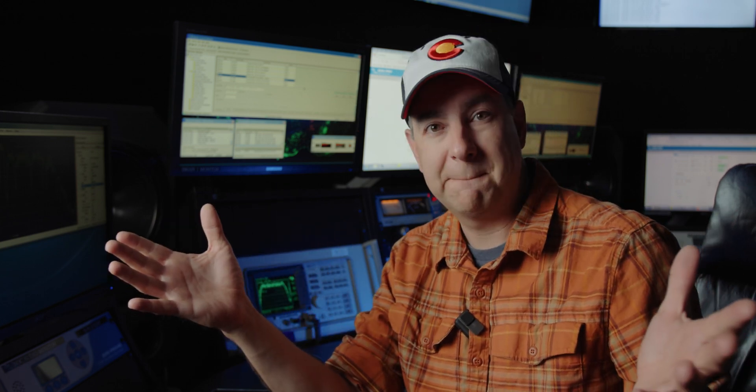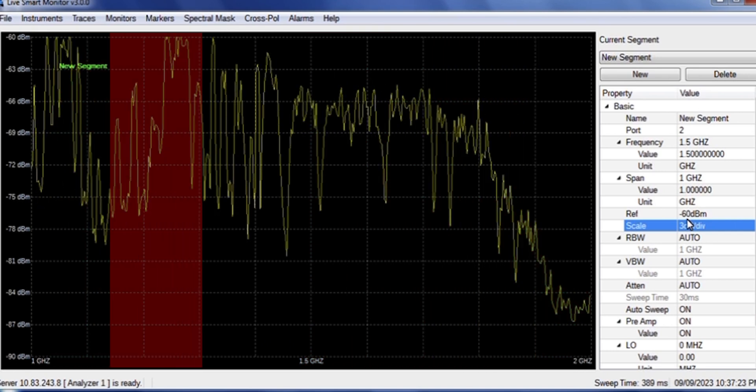Now, what our resolution bandwidth is, is how wide that window is. So if you are looking at a very large signal, a wider resolution bandwidth is totally fine. But if you need to see things that are narrower, or if you have multiple things that are smaller next to each other, if your resolution bandwidth is too wide, you're only going to see one signal, you're only going to see the one big signal, because that window only measures RF once in that window. If you have multiple signals in there, then you need to shrink that resolution bandwidth down. So that way, that window is smaller, and that'll give you more points to be able to see.